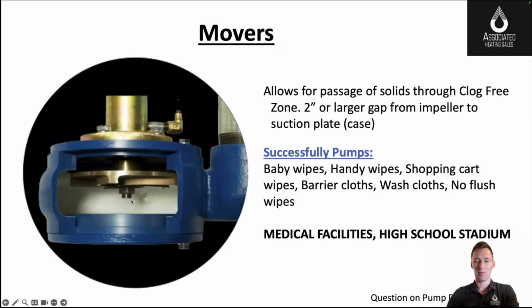People have loved these. We've got a couple of hospital systems across the state that use these exclusively and have been really happy. So if you are running into clogging issues, these wipes that everyone's using, different applications where they have no control over what's being flushed, the Weil mover pump has been great. Definitely pumps things along the line to the larger pipe sizes, the municipal systems, and getting them out of your end user that's at the commercial level system, and not wrapping up a pump and burning up a pump has worked quite well.